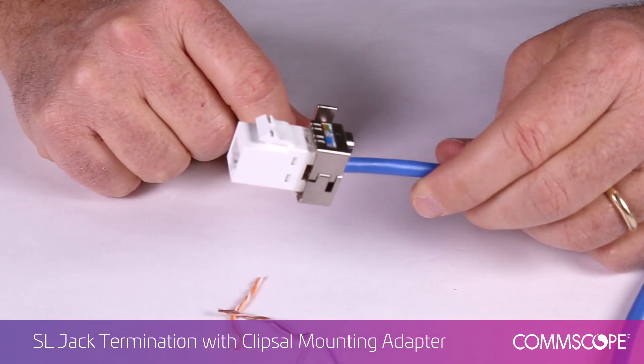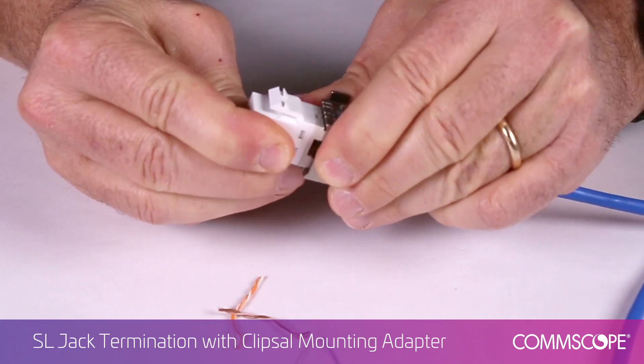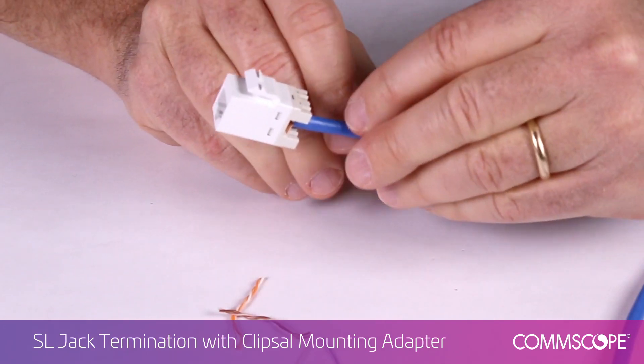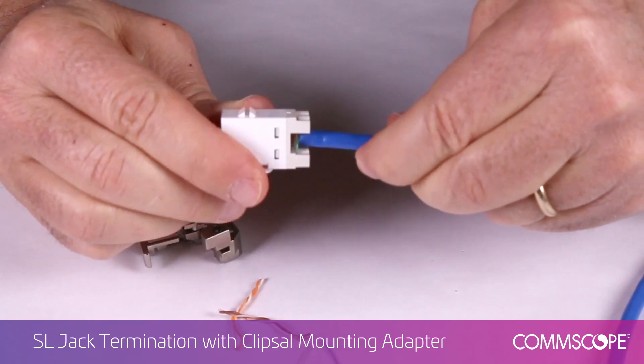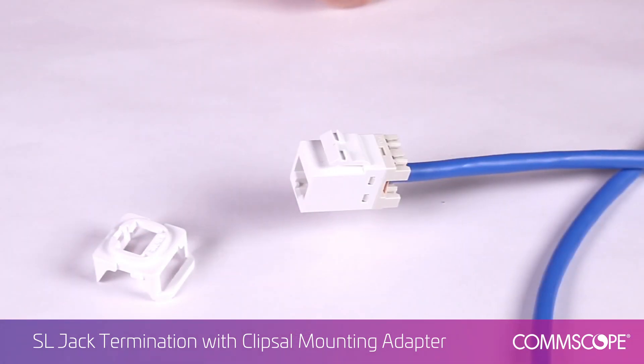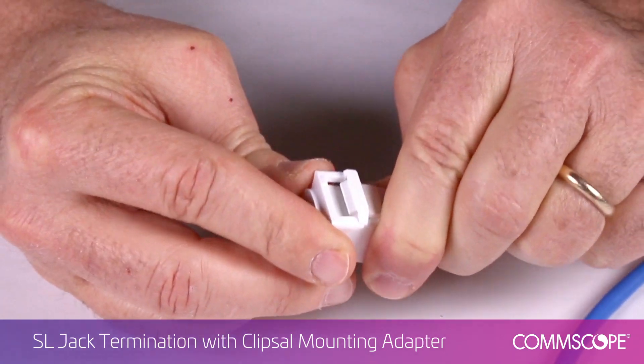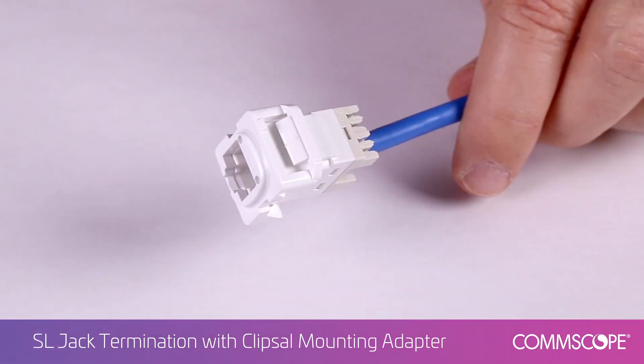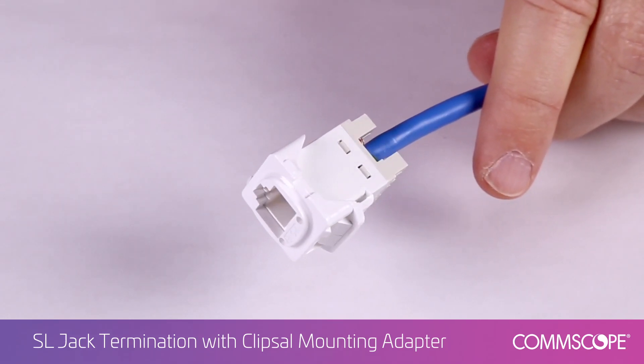To remove the jack from the lacing fixture, gently rock the jack from side to side to release it from the fixture. Visually inspect the terminated jack to ensure proper seating of the conductors. Install the Clipsal adapter onto the front of the jack — the adapter should be aligned on the bottom side of the jack, then snapped over the latch on top. The terminated jack may now be installed in the Clipsal style faceplate.